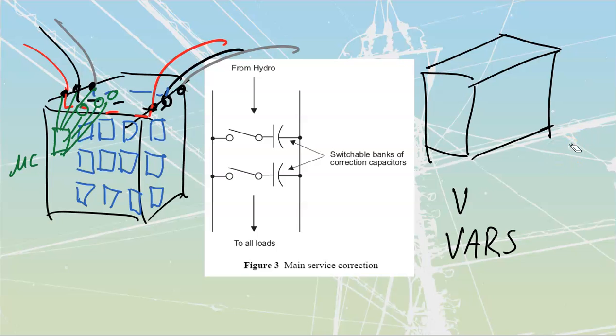It's also going to be rated for frequency. These are my top three ratings. You need to make sure the frequency is correct — if you use something rated for 50 hertz on a 60 hertz system, or 60 hertz on a 50 hertz system, it's going to screw up the capacitance. This is very critical on pieces of imported equipment.